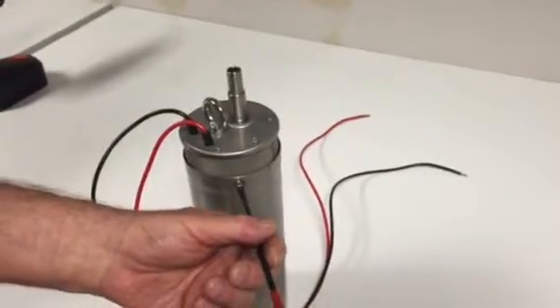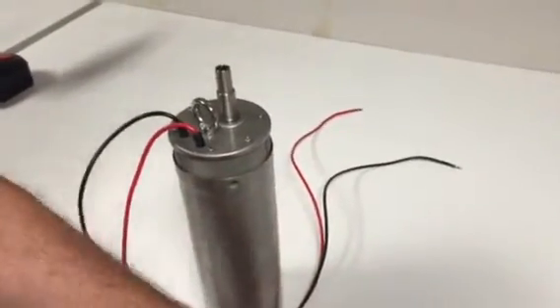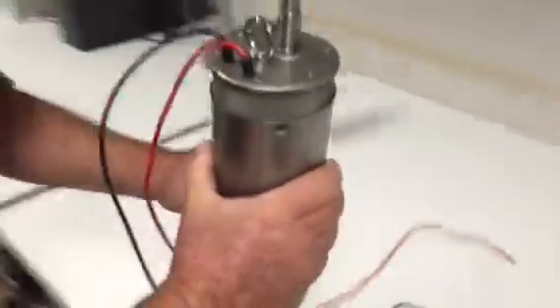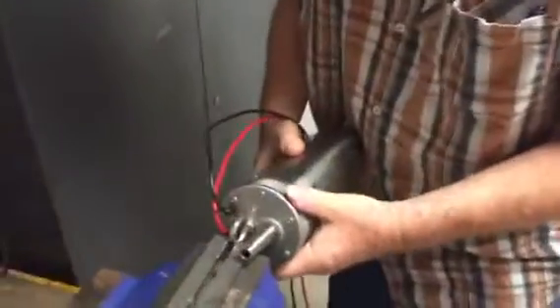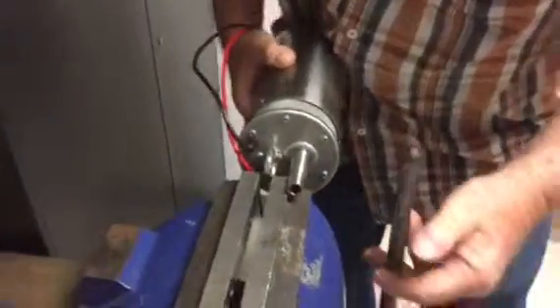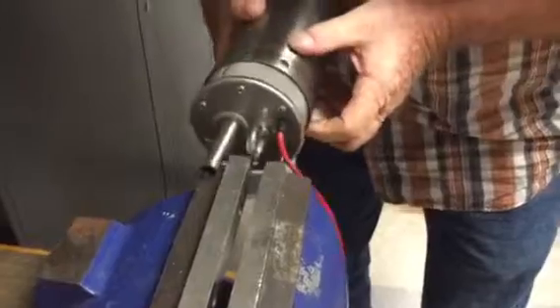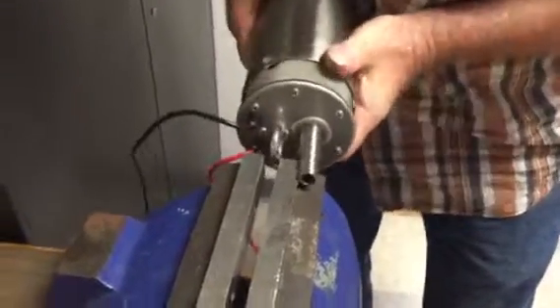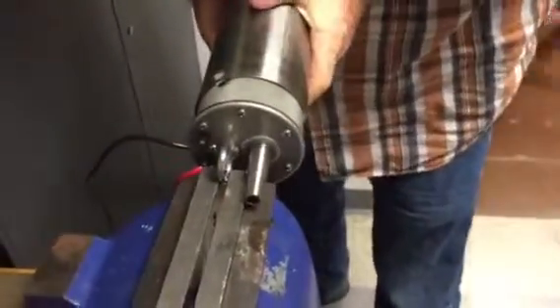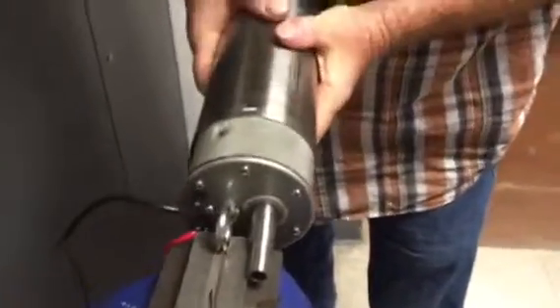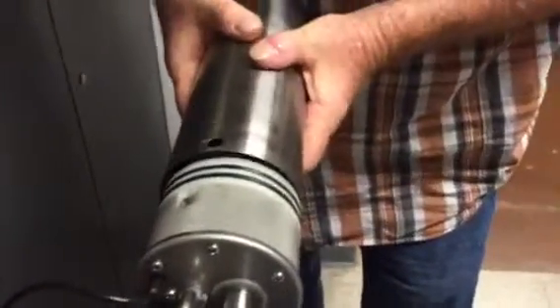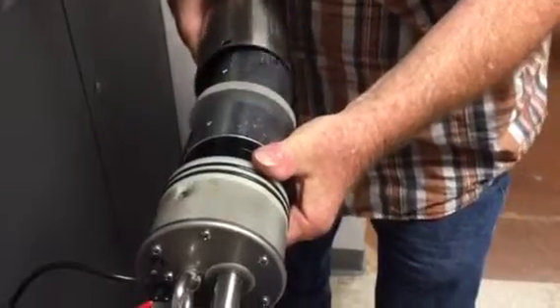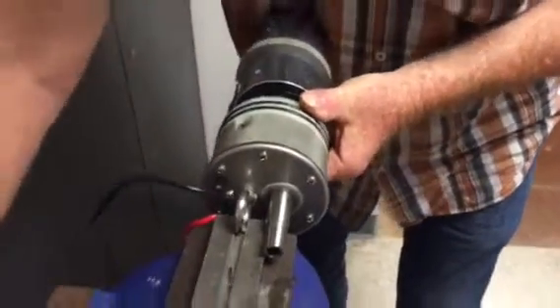The three bolts secure the can onto the pump. We proceed now, ideally with a vice grip, to utilize the safety cable loop to secure onto a vice grip in such a way. The can is going to have some vacuum, so turn in the motion seen here, side to side, as you pull the can out.